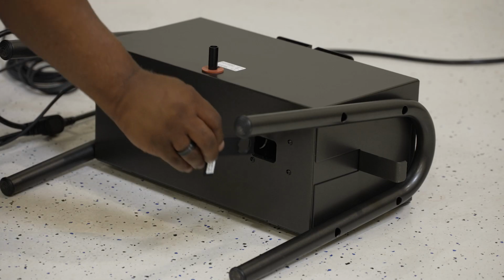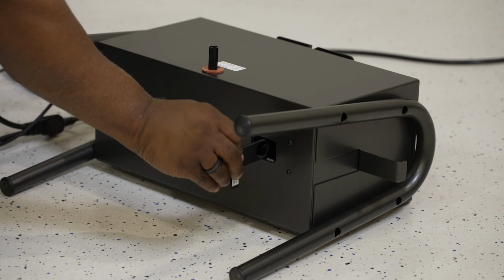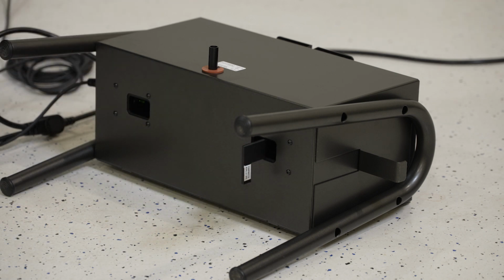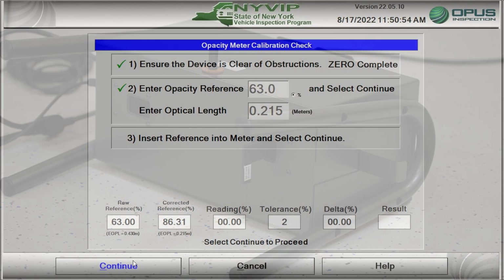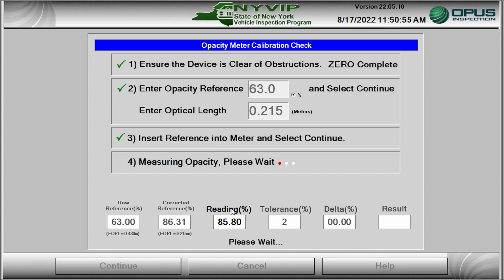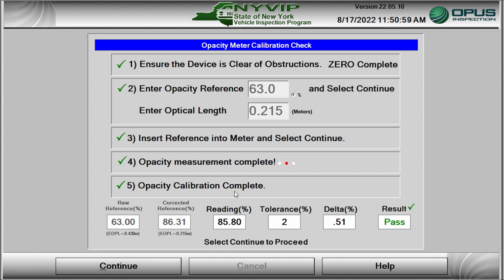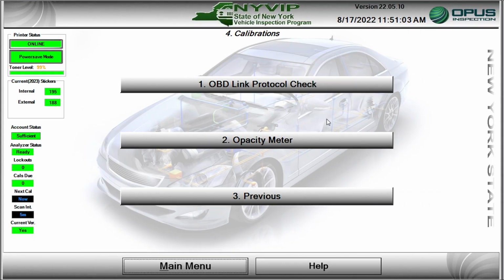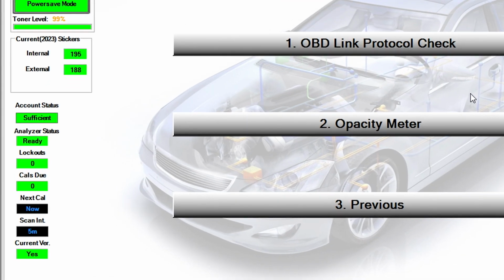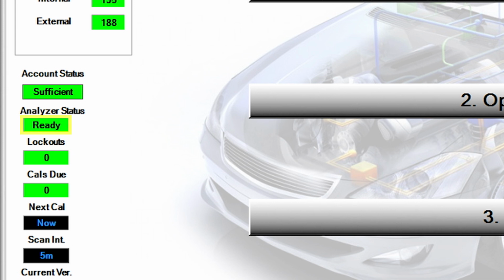Insert the reference glass into the slot in the opening on the bottom of the meter, furthest from the power cord and the on-off switch. Click the Continue button to automatically complete calibration. Click the Continue button again. In the Status section of the screen, the Analyzer status icon will be green with the word Ready displayed, and the CALS DUE icon will be green with 0 displayed.